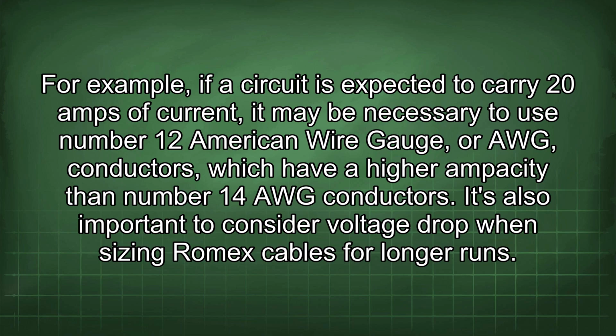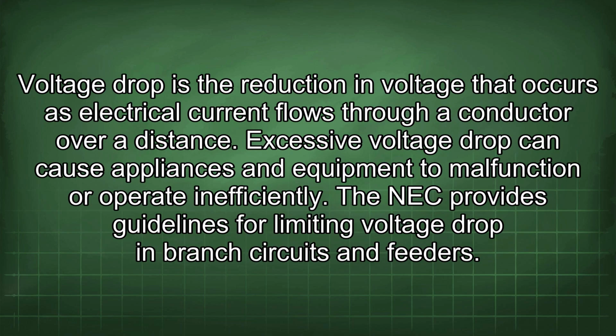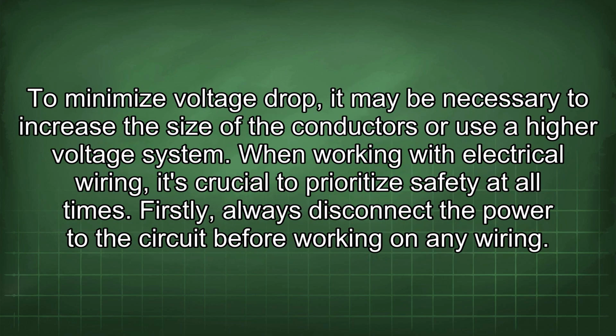It's also important to consider voltage drop when sizing Romex cables for longer runs. Voltage drop is the reduction in voltage that occurs as electrical current flows through a conductor over a distance. Excessive voltage drop can cause appliances and equipment to malfunction or operate inefficiently. The NEC provides guidelines for limiting voltage drop in branch circuits and feeders. To minimize voltage drop, it may be necessary to increase the size of the conductors or use a higher voltage system.